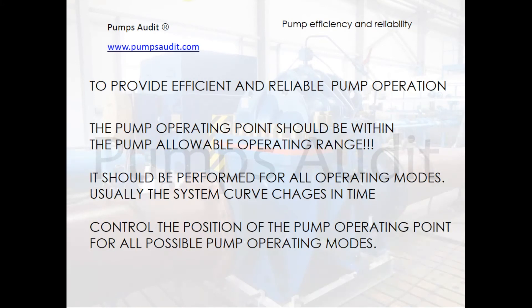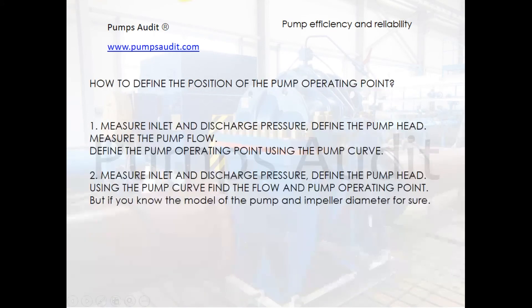Some rules for efficient and reliable pump operation: the pump operating point should be within the allowable operating range for all operating modes, since the system curve changes over time. Control the position of the pump operating point for all possible operating modes. Here are some recommendations on how to define the position of the pump operating point.